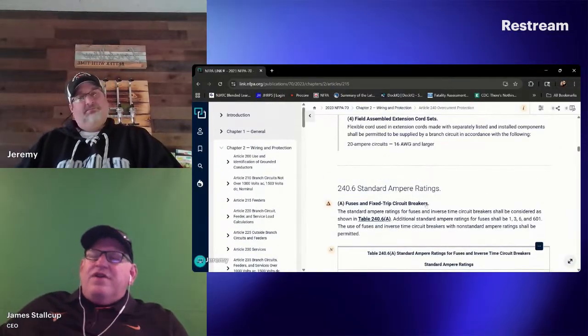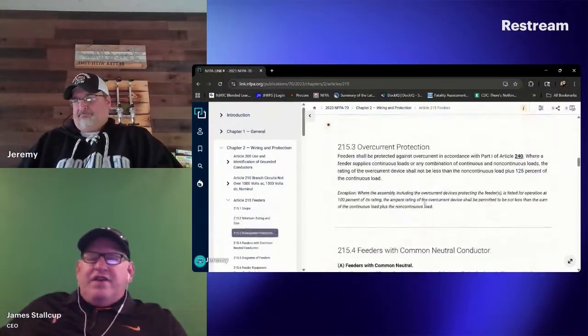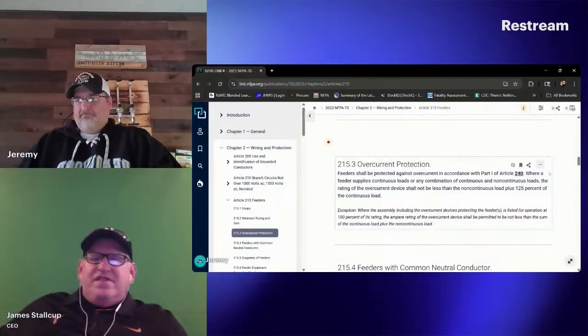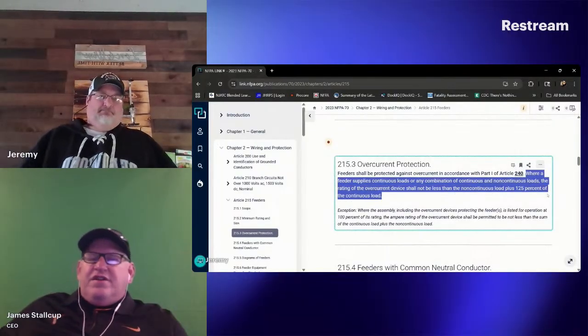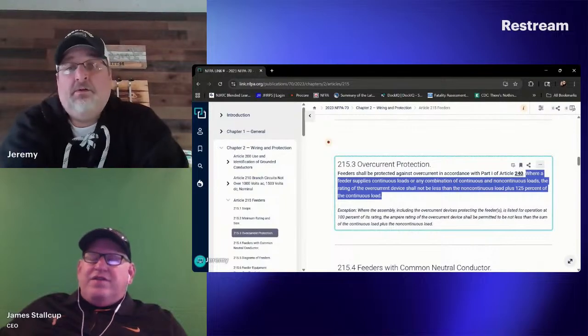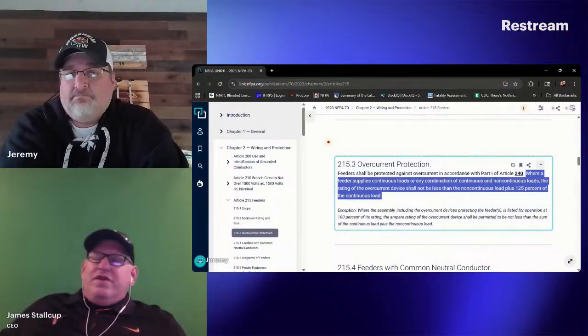But when I go look at 240.4(C), it tells you to do your calculation, the size and capacity of your conductors. And then once that's decided, it tells you the conductors have to be equal to or greater than the rating of the overcurrent device. But it doesn't say that when I look at 240.4(B). And that's what I'm saying.